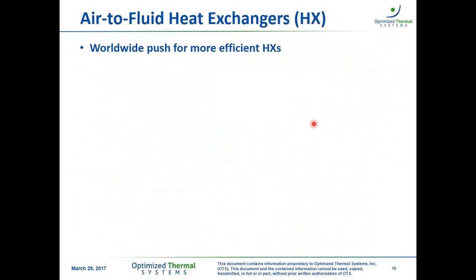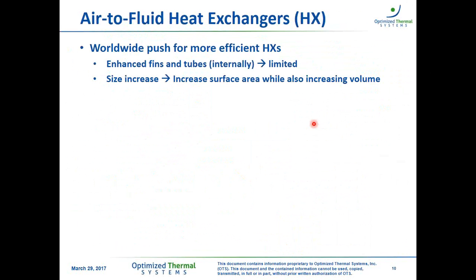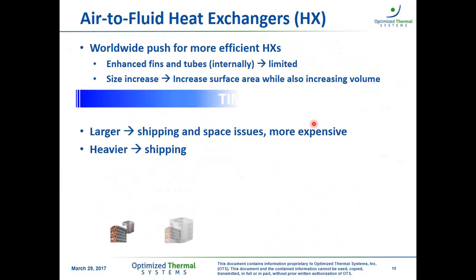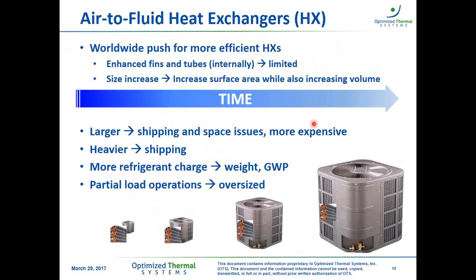So we have this worldwide push for more efficient heat exchangers, and based on what we saw in the initial slides, it seems like we have everything figured out. How can we get more efficient heat exchangers? Let's add fins and enhance them and enhance the tubes internally. What happens nowadays is that we have basically reached the limit of what state-of-the-art tube fin heat exchangers can do. So the solution to push for more efficient heat exchangers is an overall sizing increase. So we're increasing the surface area while also increasing the volume, not necessarily increasing the compactness of these heat exchangers. So over time, what we're seeing is a gradual enlargement of these heat exchangers, which obviously affects shipping and space issues. They're more expensive, heavier, they consume more refrigerant charge, and they will obviously be oversized for many operating conditions, which can reduce the system's performance.